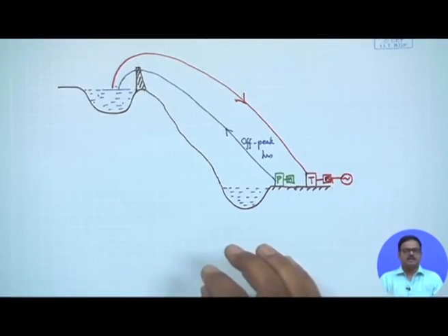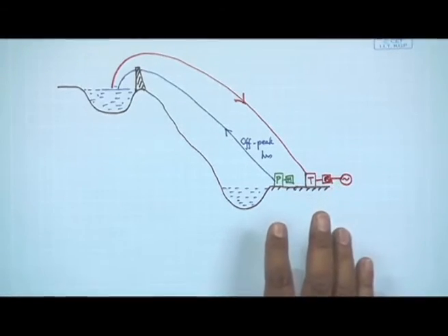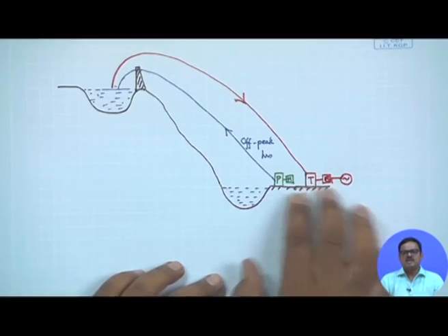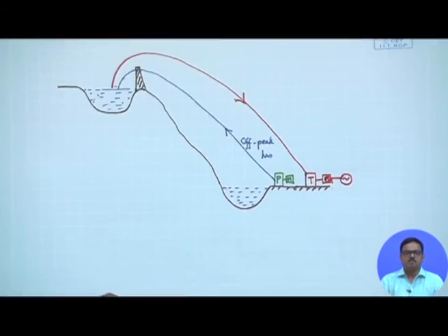The way I have drawn the schematic is definitely pictorial. In reality, the pump and the turbine are not necessarily separate turbo machines. As we know from our mechanical background, a Francis type of turbine can work both as a pump and a turbine. From an electrical engineering viewpoint, if you have studied electric machines, you would know that the same rotating machine can be used both as a motor and a generator. So, the pump and motor as one assembly and turbine and generator as another assembly are not necessarily two separate assemblies. Many a time they are the same.